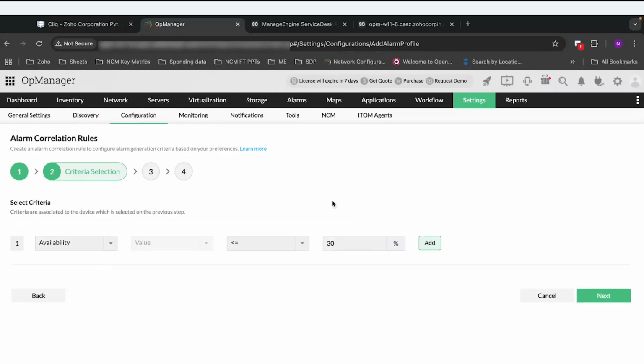I've given the value as 30%. This means the 10 UPS systems selected represent 100% as a whole. So when it reaches 30%, that means 7 of the critical UPS have gone down, leaving only 3. This will be the threshold value of 30%. Once this is reached, the bank must know all 7 UPS have gone down and need to immediately work on restoring them.